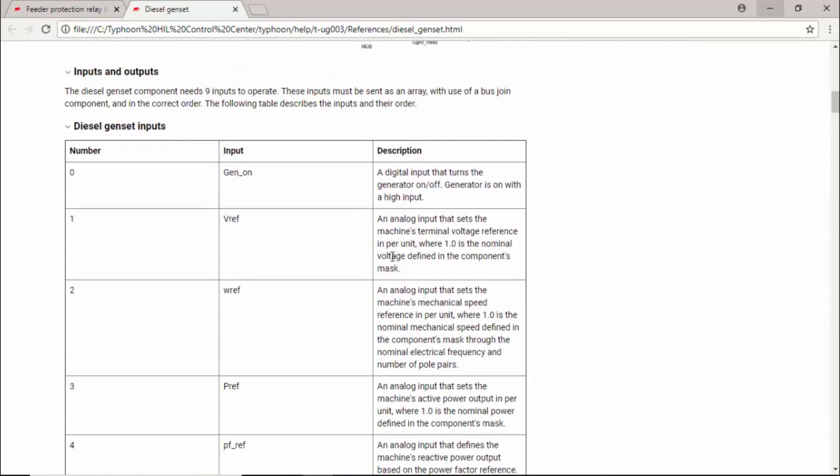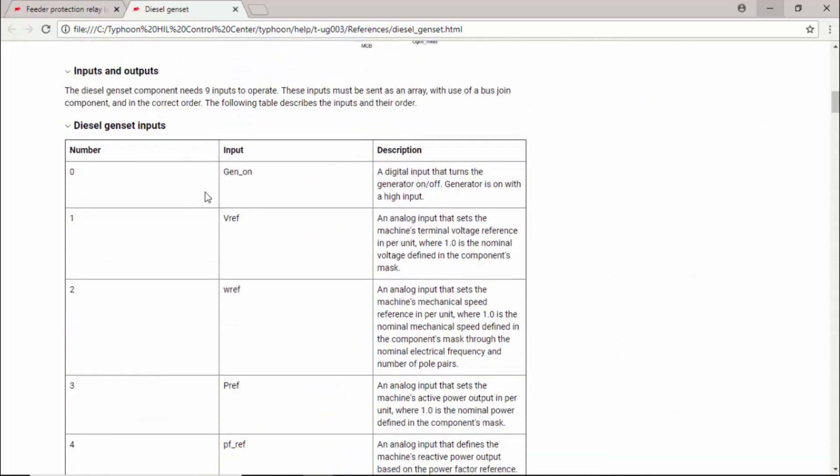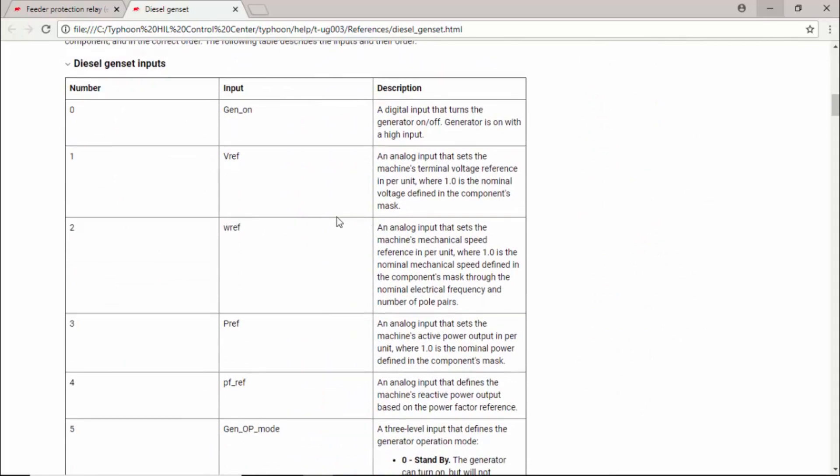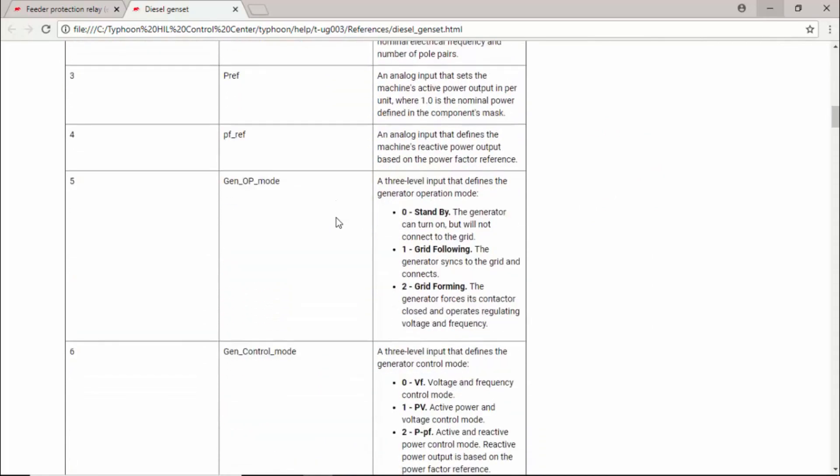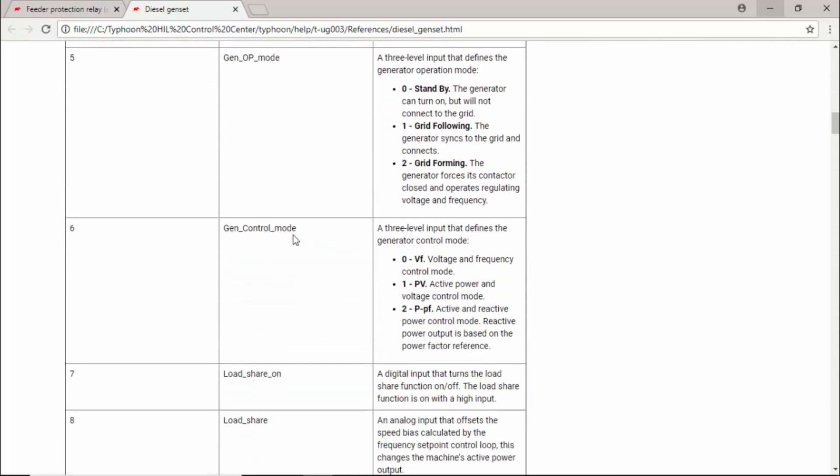For example, if we scroll down to the diesel genset inputs, we can see that gen control mode, the input number six, is actually a three level input that defines the operation mode of the genset. It can be zero, meaning VF, so it will control voltage and frequency. It can be one, so it controls active power and voltage. Or it can be two, meaning PPF, so control active power and power factor. This is how you understand what you need to provide and what it will do to your model.